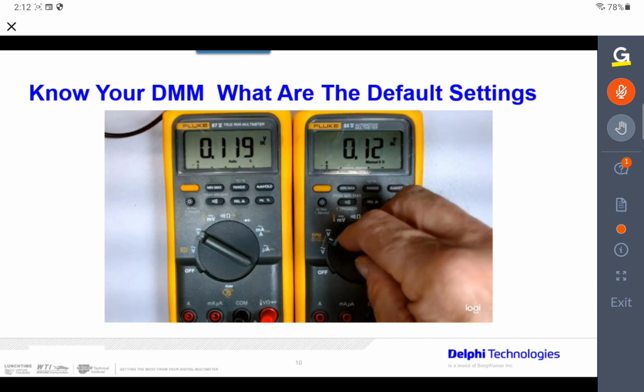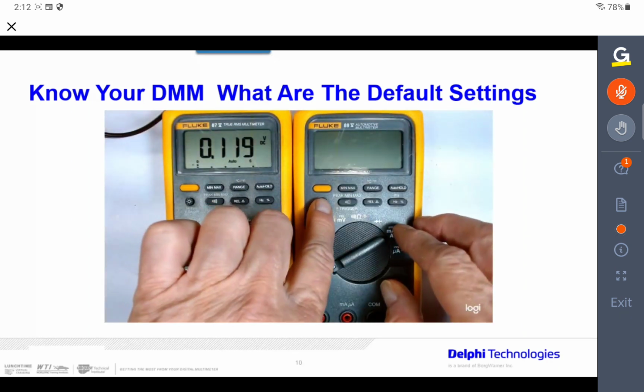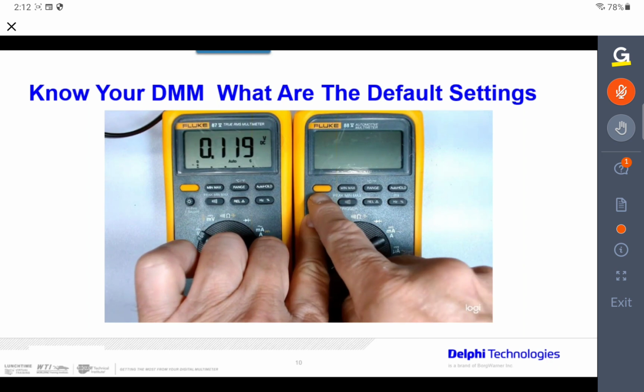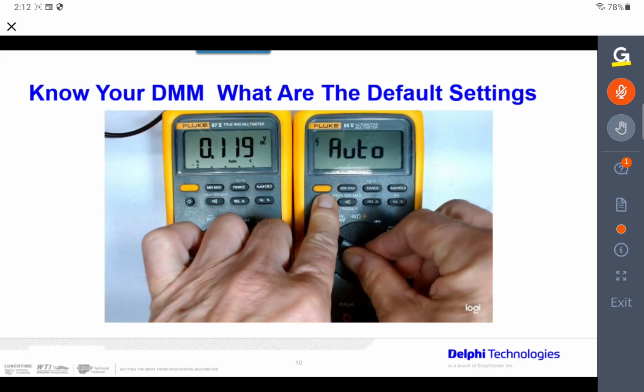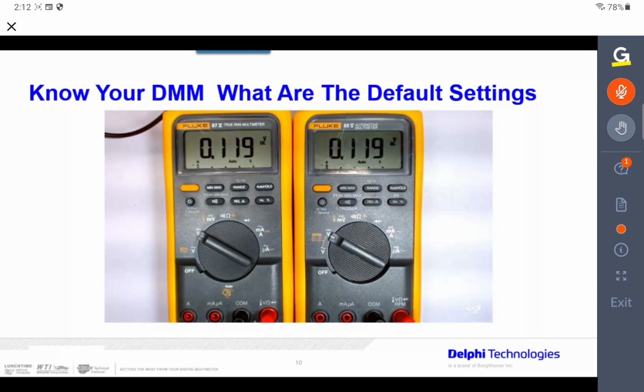So I'll turn the meter off, push the high resolution or light button, flip my meter up, and notice it went to auto. Both meters now read the same, and my bar graph is better, working exactly like the other one. So using auto makes the bar graph work that much better.